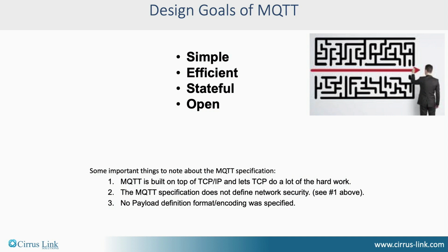The spec doesn't define any network security. They say, oh Arlen, OPC-UA defines security, DNP 3.0 defines security. Well, go back and look at number 1: MQTT is based on TCP/IP. If we would have defined how to do security, I wouldn't be here talking today. The fact is MQTT can move at the pace of whatever the latest technology of TCP/IP security is.